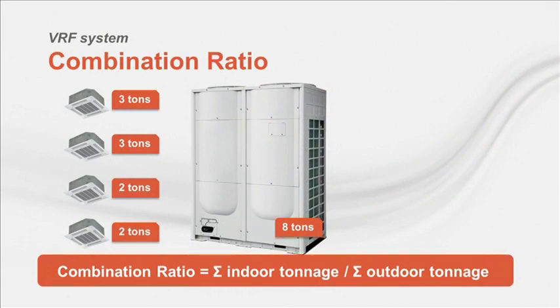Staying under the combination ratio prevents 2 problems. First, it prevents an imbalance in the refrigerant charge when the system is in total cooling or total heating. If this were to occur, the unit would shut down on a safety. Second, it allows for some zone load diversity inherent in most buildings due to varying occupancy patterns and loads. Indoor units are normally cycling on and off based on individual zone requirements. Because the combined loads of the indoor units aren't constant, it allows the total connected capacity of the indoor units to exceed the capacity of the outdoor unit.